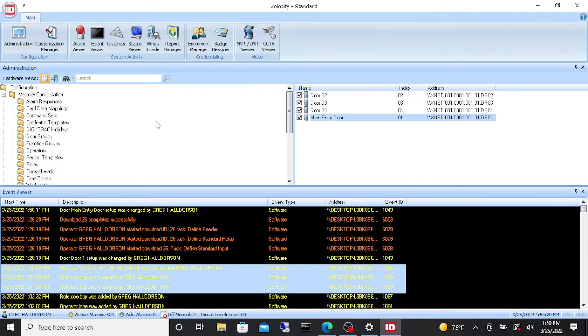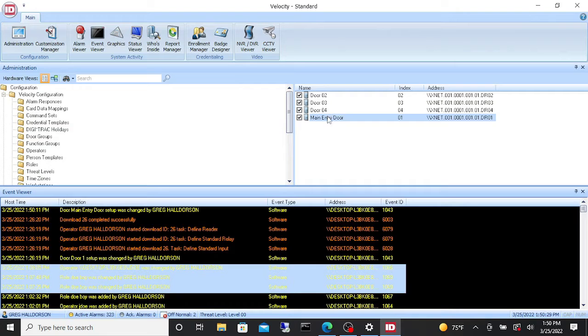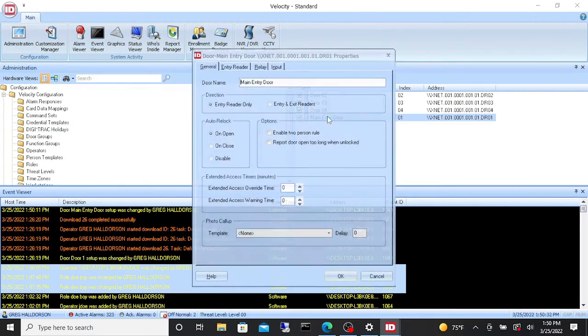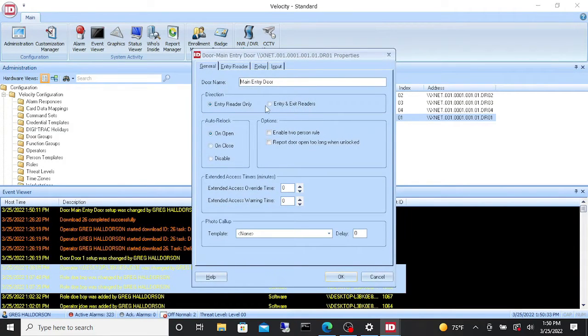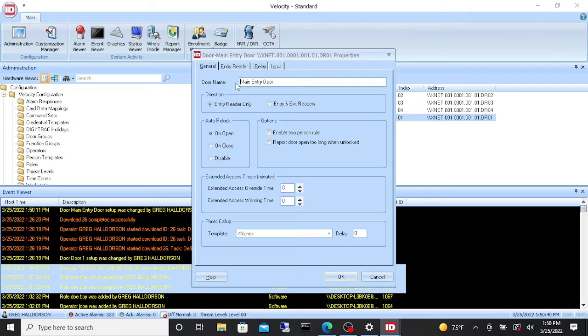To set up a door to unlock automatically, you're going to add a time zone to the relay of that door. So we're going to go to our door, say the main entry door, and let's say you want it to unlock at seven in the morning and lock at five at night. So we opened up our door properties.